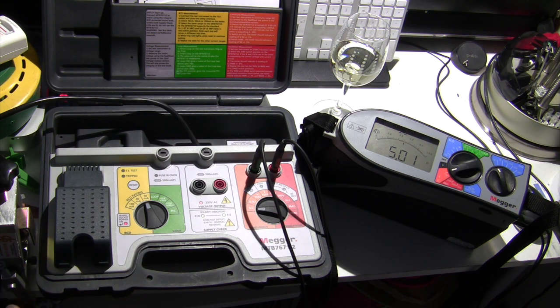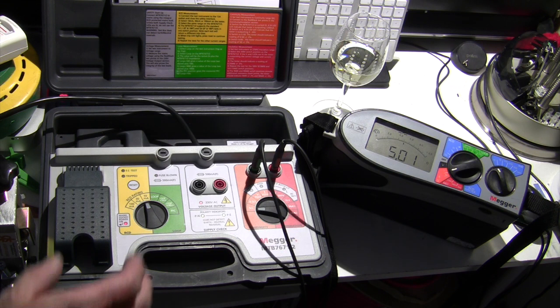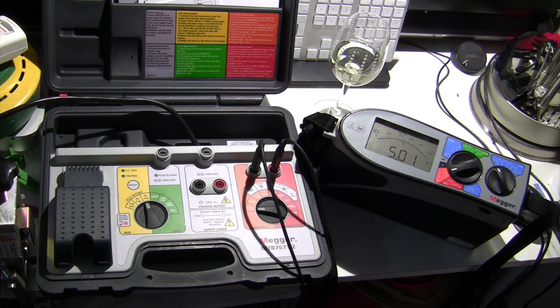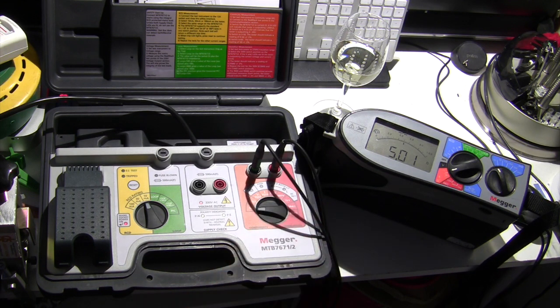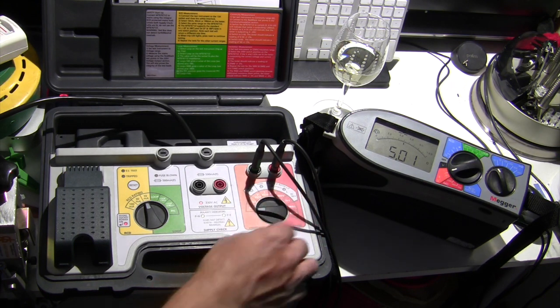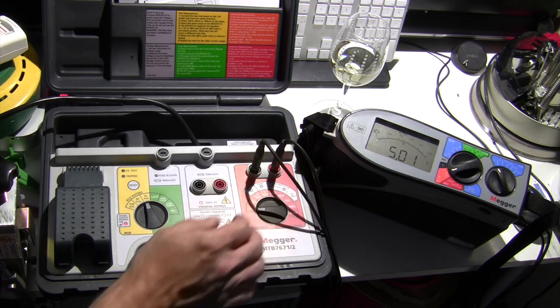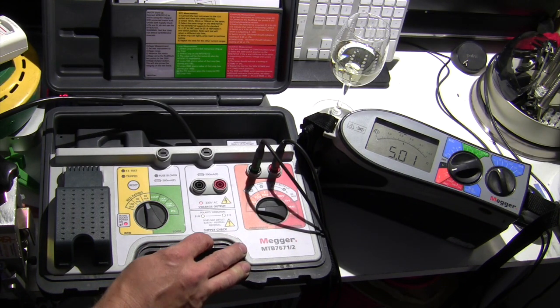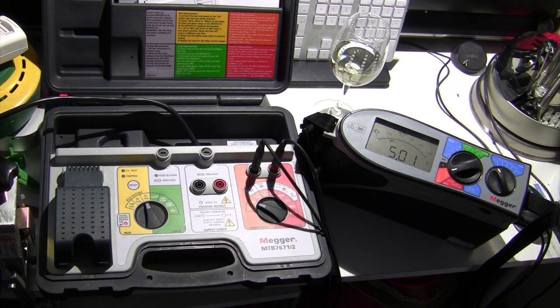It doesn't really matter if this goes out of calibration to a certain extent. So long as both testers are reading the same kind of results, then we know that this is putting out a constant number. If obviously the testers disagree on the output of this thing, then we'll have to have a closer look at the leads and the testers themselves, and maybe send them off for checking to make sure that they're still in calibration. I haven't had any problems with calibration. They do take the odd fall off the ladder or end up out in the cold on dusty first fix sites. So despite appearances, and it is in pretty good nick still after all these years, they do get kicked around a bit, so you never know when something's going to not quite work the way it should.